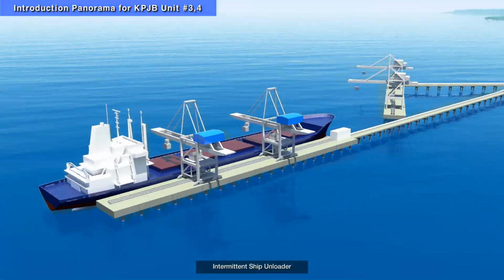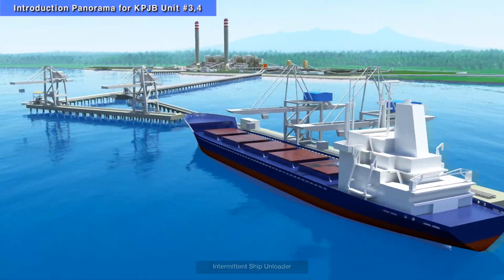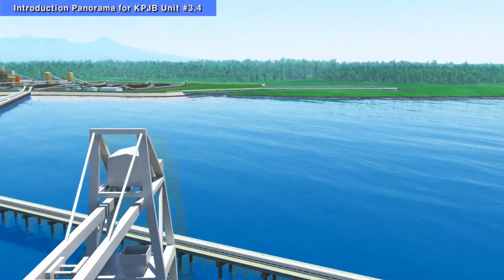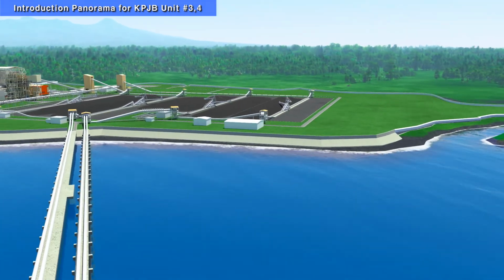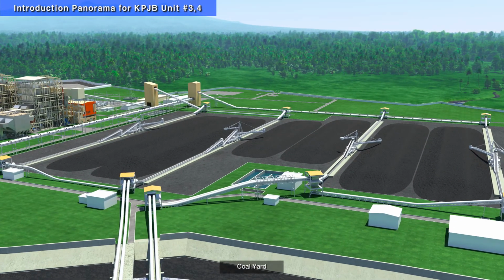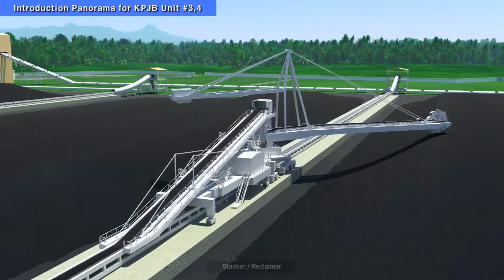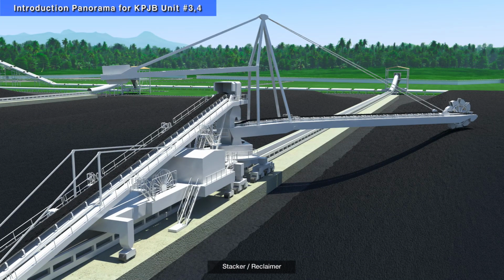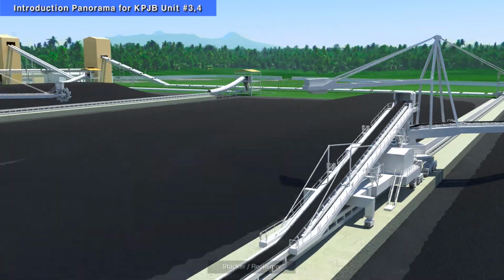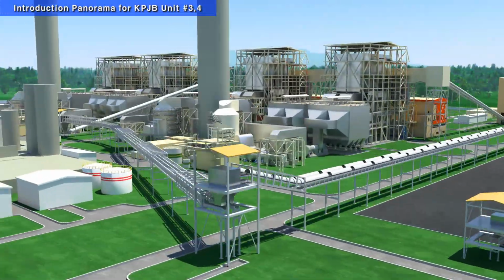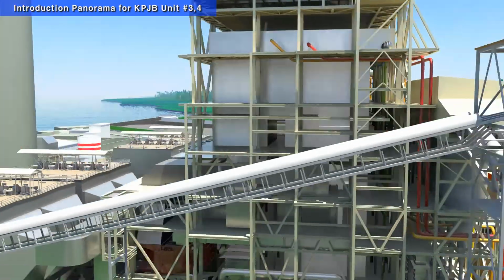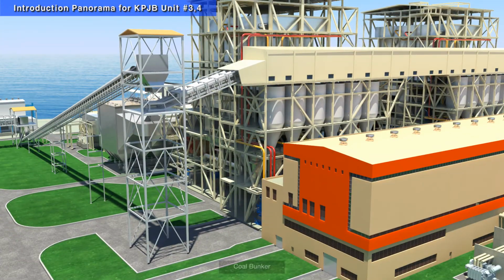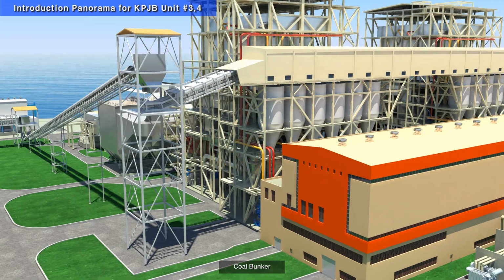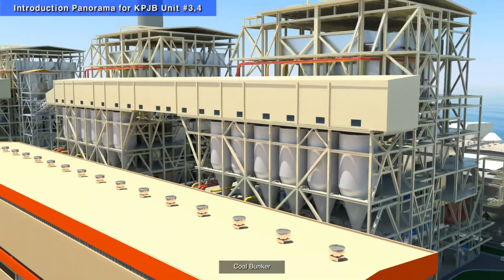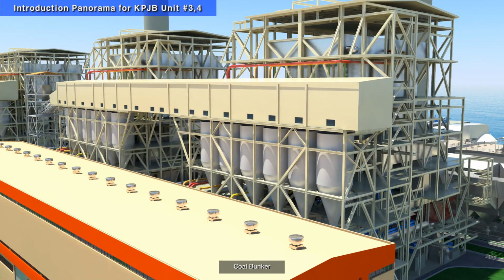Bituminous coal, which is used as a fuel, is transported by 70,000-ton Panamax vessel from Kalimantan and is unloaded by 2 ship unloaders installed at the coal jetty. Such coal is transported by belt conveyor and stacked by 2 stacker reclaimers in the coal yard, whose storage capacity is 660,000 tons. Coal stored in the coal yard is forwarded to the coal silo through stacker reclaimer, conveyor, and tripper.